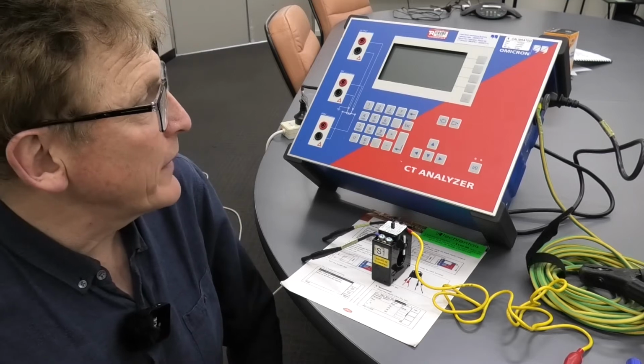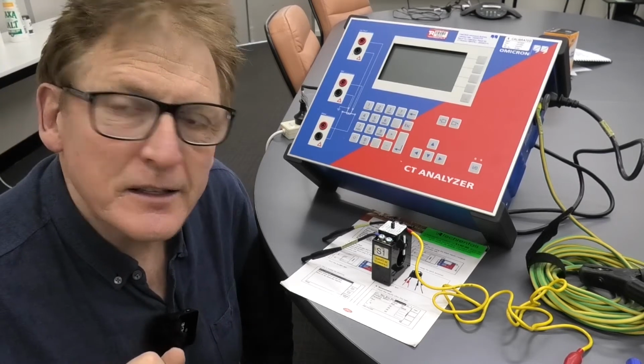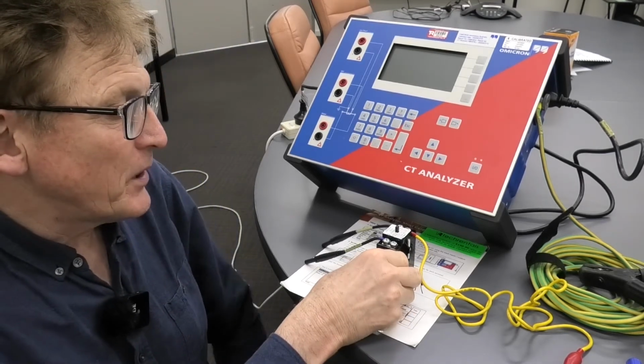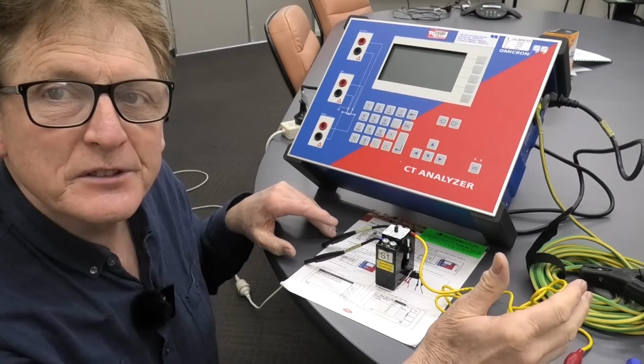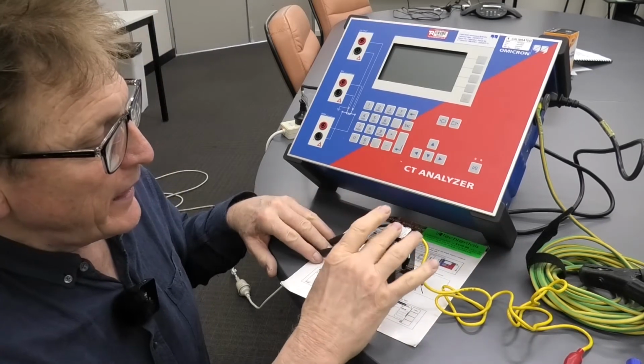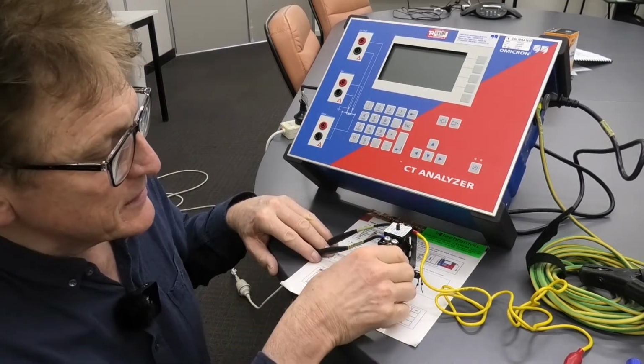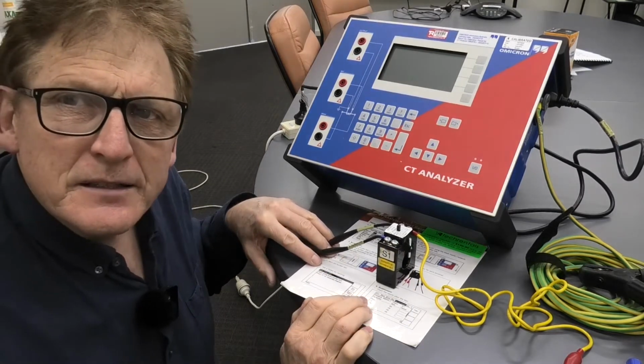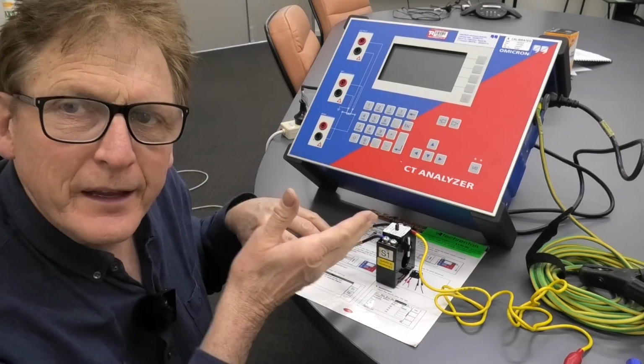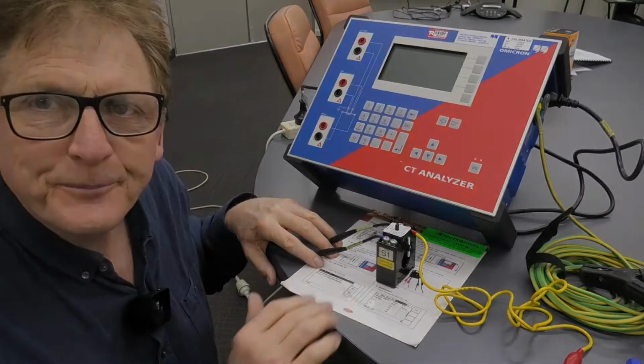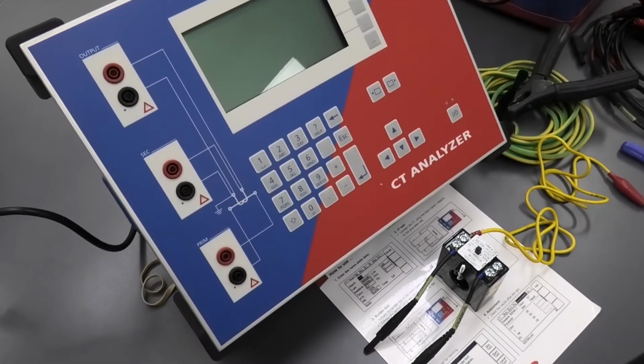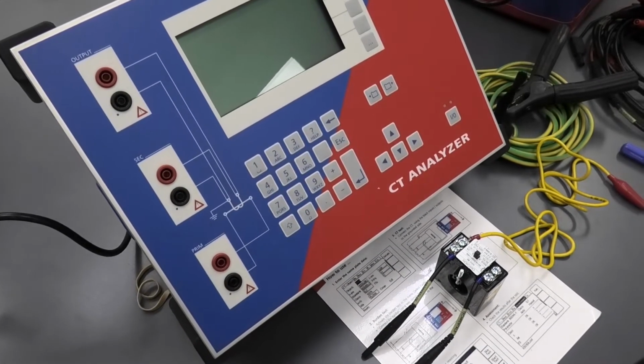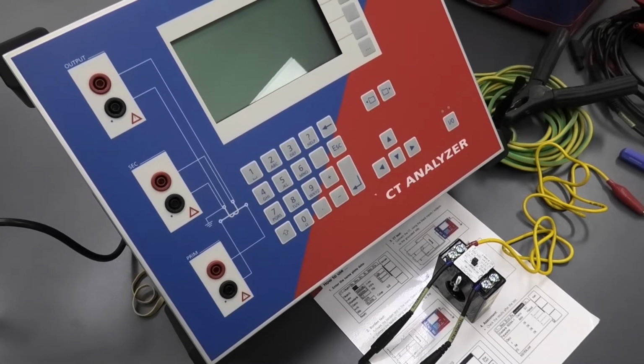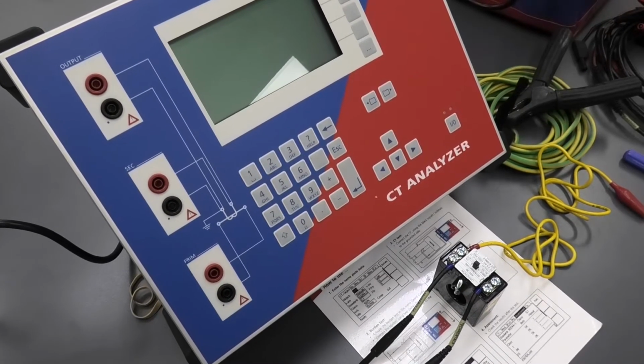Just going to have a quick look at the OMICRON CT Analyser. Now, we supplied in the kit various cables, etc. And we're just going to run, this is a CT which is in the kit. So we'll just run and test this CT. Now, we need to wire the instrument up according to the diagram on the front here. So we've got the primary side and the secondary side.